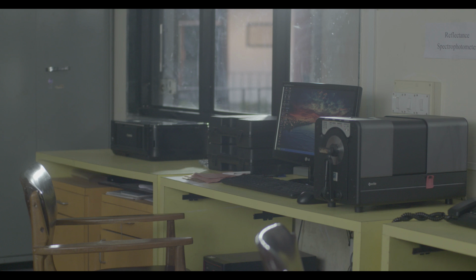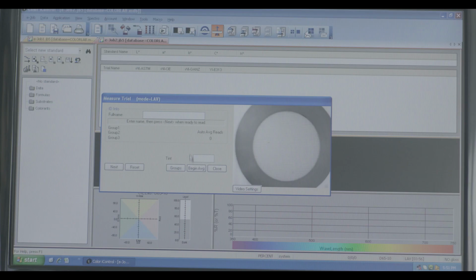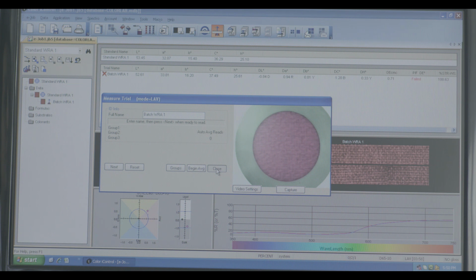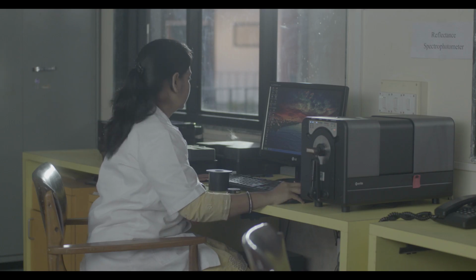Once the instrument is initialized, the second most important step is the instrument calibration. But before calibration, we need to select the suitable aperture size as per the size of test specimen. For very small samples, we can select small aperture, SAV, that is 6 mm. Then comes medium aperture, MAV, that is 10 and 17 mm. And for larger samples, one can use 25 mm LAV aperture. After adjusting aperture, next is lens positioning as per the aperture size. Now the instrument is ready for calibration.